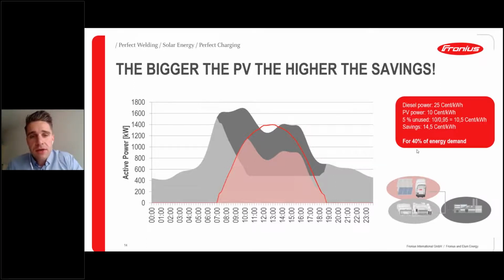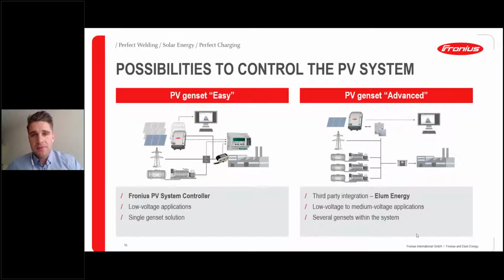The only thing you need here is a kind of regulation, because you see there are parts of the day, maybe 1 hour, 2 hours, where the energy coming down from the PV system exceeds the actual load, and therefore we are in need of such a controlling mechanism. Yes, you see it, the control of the PV production is necessary. And therefore, we have 2 different possibilities here at Fronius, which I've listed here now, that is basically depending on how many gensets you have in your system.